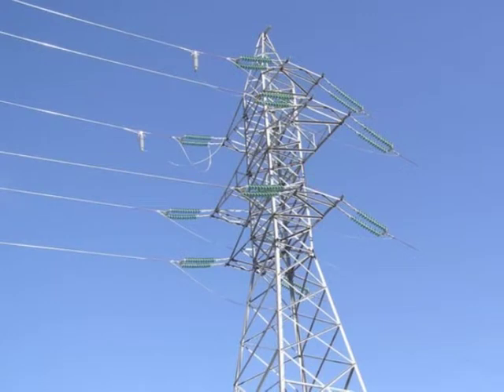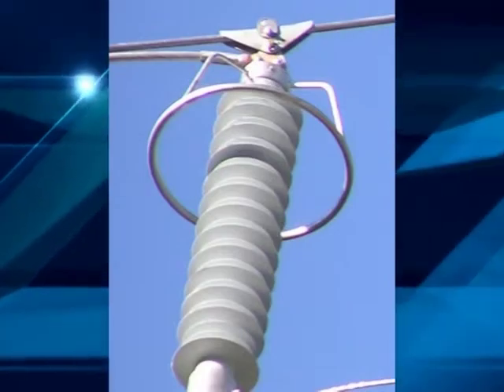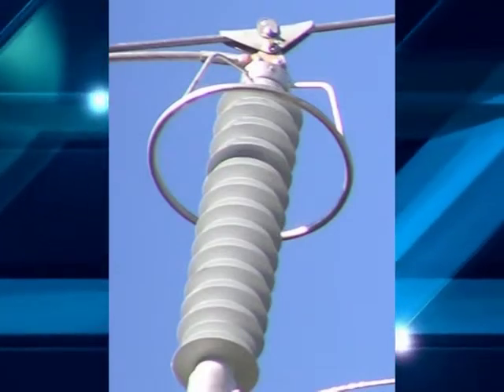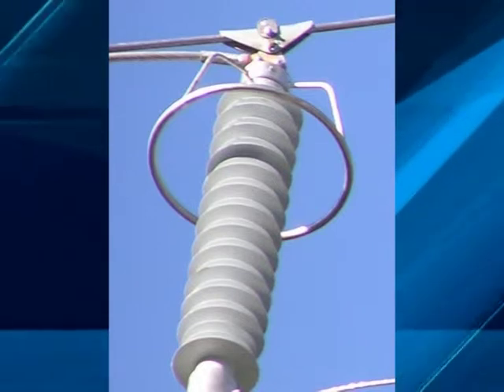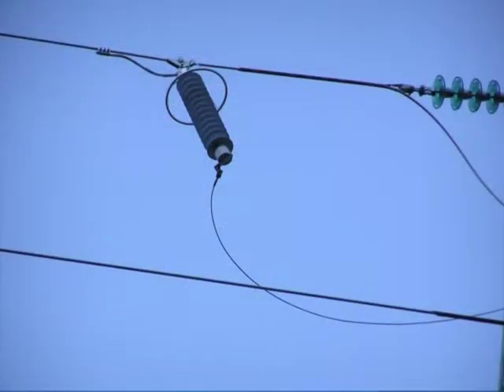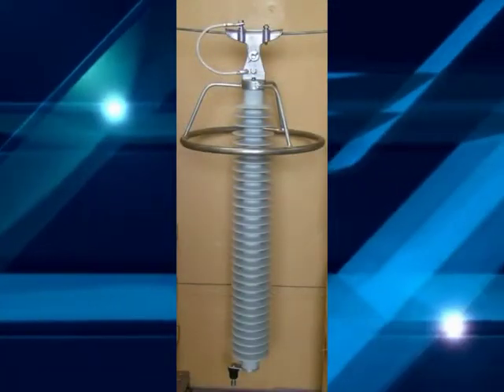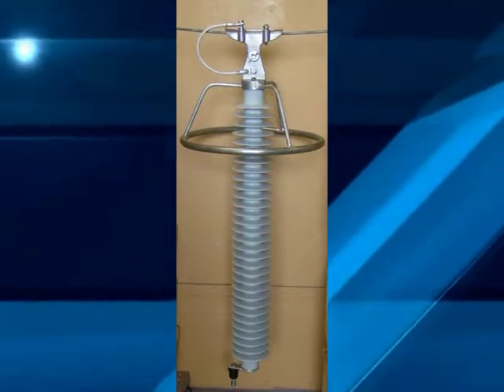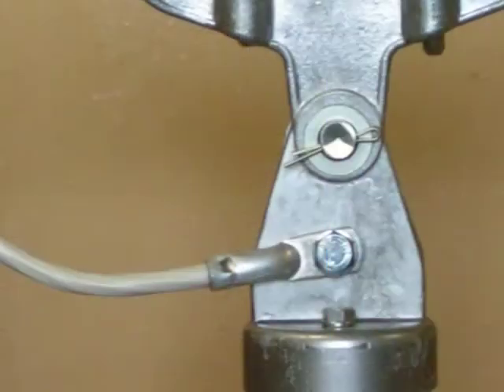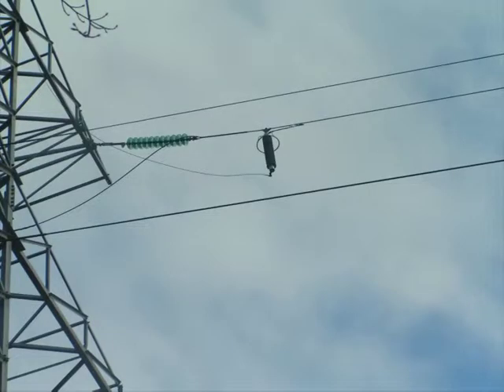Surge arrestors are also used on overhead lines in glaze ice areas where suspension of lightning protection lines is not practical. This principle of protection was successfully applied to a new generation of overhead lines for Olympic facilities in Sochi. Metal oxide surge arrestors with gaps of our company Polymer-Apparat were installed only in the upper phases and replaced the lightning protector line. During the operational process, damage to linear arrestors is unlikely but possible.